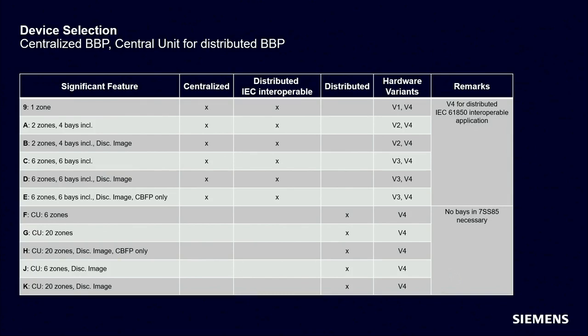We have A, 2 zones, 2 independent single buses, and we have B, which has also 2 zones, but it has a disconnector image. This means with significant feature B, we can deal also with one double bus. And then we have the C, which is also without disconnector image. So this means 6 independent single buses. We have the significant feature D, which means 6 zones with disconnector image. This would allow a triple bus bar with a sectionalizer inside, for example, or a double bus bar with a sectionalizer in a transfer bar or anything else.